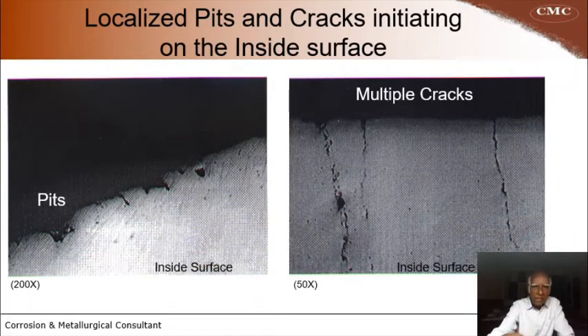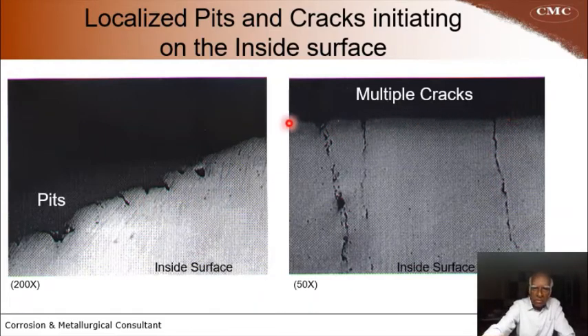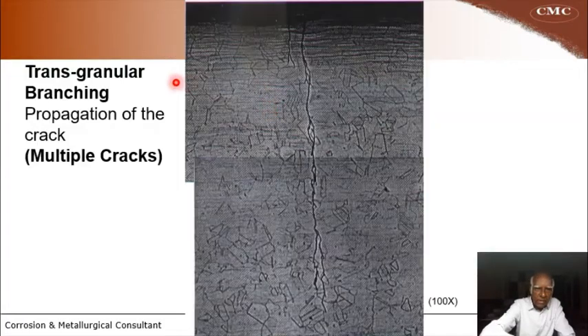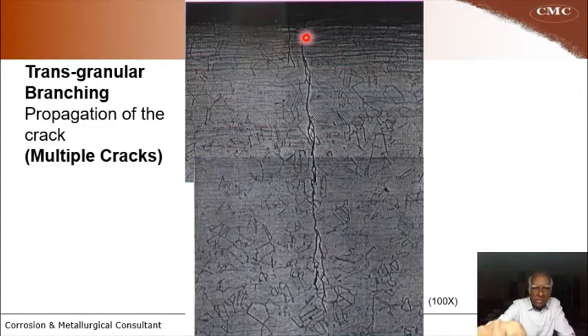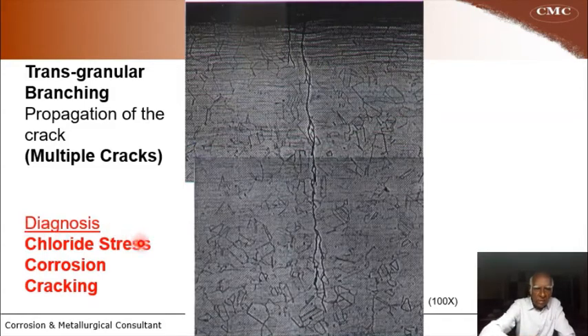These are the typical metallographic structures in the as-polished condition. It shows localized pits on the alcohol surface — this is the inside surface where alcohol flows — along with localized pitting corrosion. You can also see multiple cracks initiating on the internal alcohol surface at several places. The previous slide shows initiation; this slide shows propagation. The propagation shows trans-granular branching cracks initiating at two or three places — this is called multiple cracks. Multiple trans-granular branching cracks indicate stress corrosion cracking. The diagnosis is therefore chloride stress corrosion cracking.